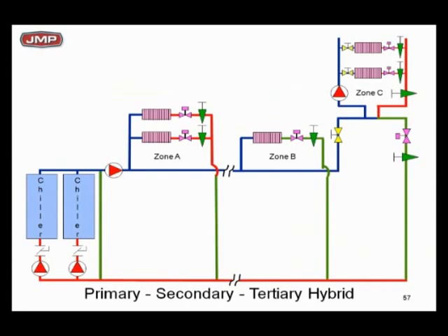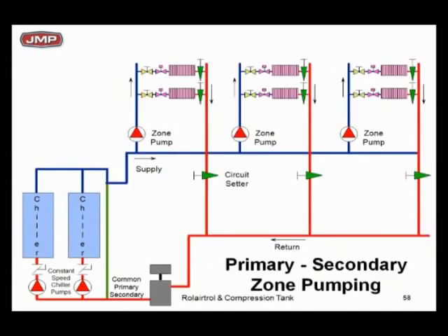Therefore, we call this primary-secondary-tertiary hybrid: it's got a little bit of primary-secondary in it, and it's got some tertiary loops as well. Another concept that's been around quite a while is the zone pump — again, it's a version of primary-secondary. Notice here we've got dedicated pumps for each chiller at constant flow, a little common pipe for the decoupler. Instead of having one big distribution pump, we have pumps in each zone. Any zone pump is pumping its zone and the distribution piping out to it — called primary-secondary zone pump.